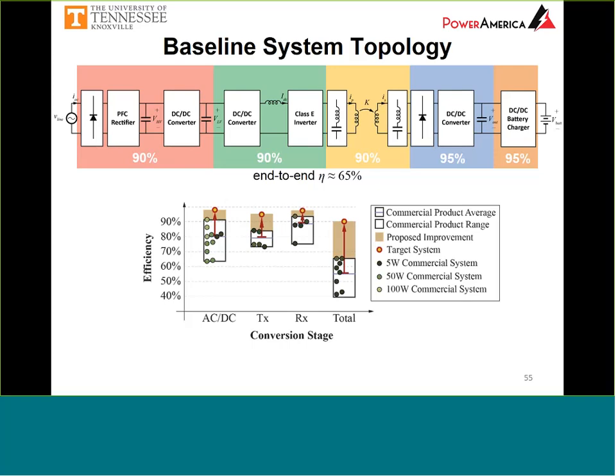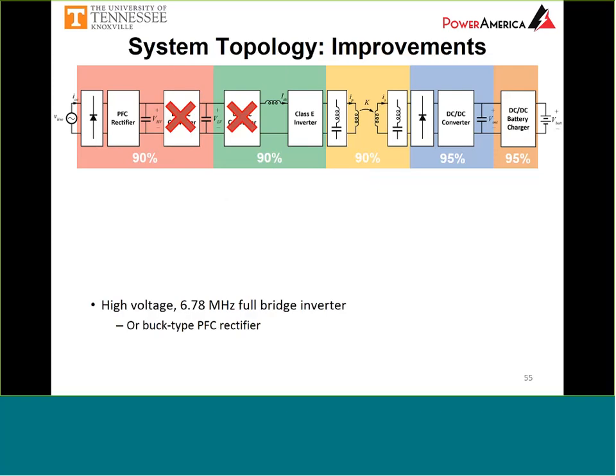The direction we're taking is to look at the overall topology and see where we can reduce unnecessary cascaded conversion stages. Looking at this baseline topology, the first thing you notice is two back-to-back DC to DC converters in between a rectifier and an inverter. From a high-level standpoint that's very redundant, since I'm taking efficiency hits from both of them.